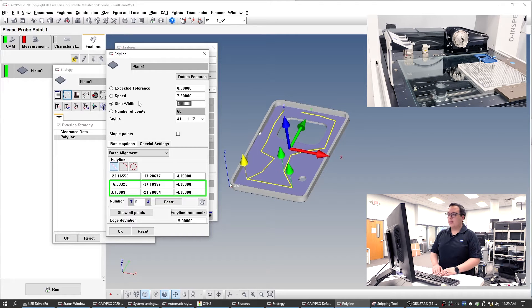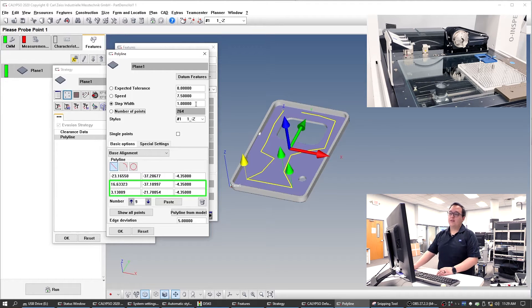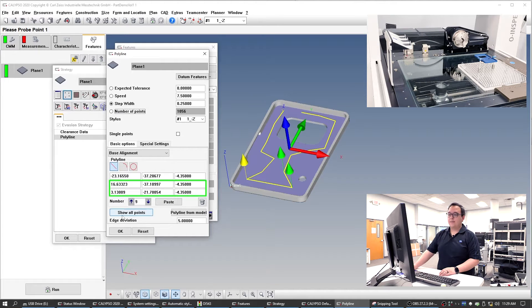Step width — let's do every one millimeter. If we do every one millimeter, we can expect 260 points. Let's do every quarter millimeter. So every 250 microns — a thousand points for that should give us a reasonable result as to what the flatness of this part is.